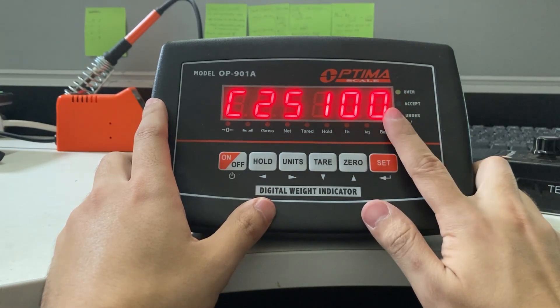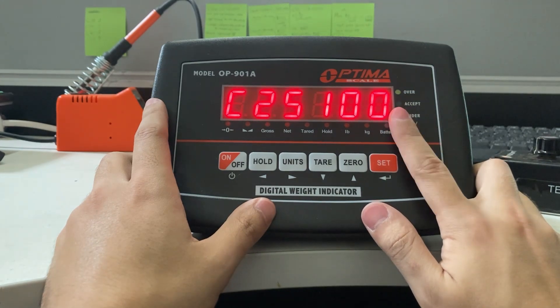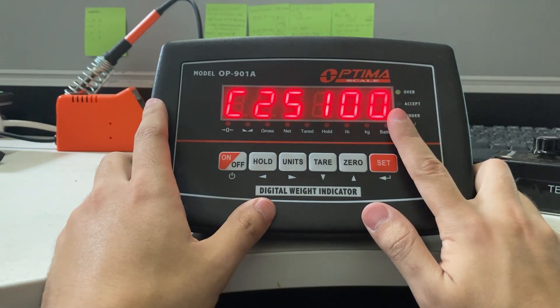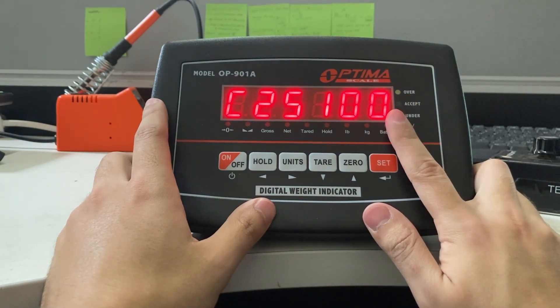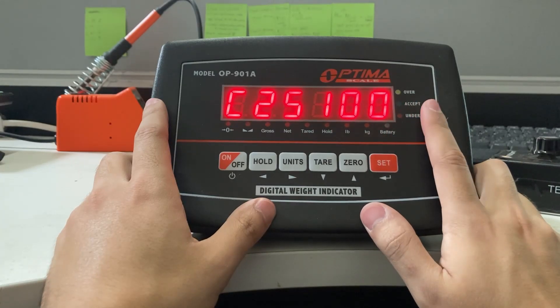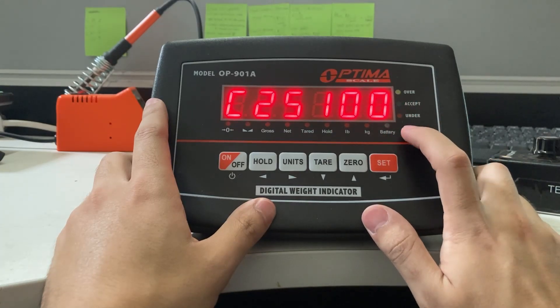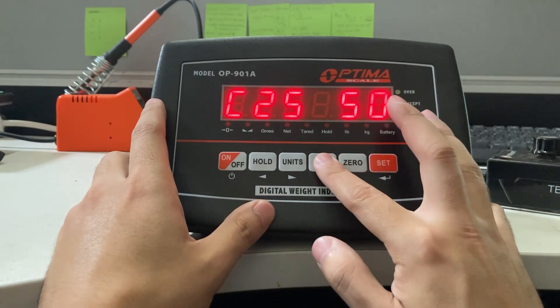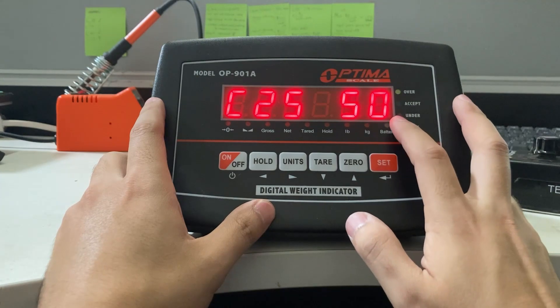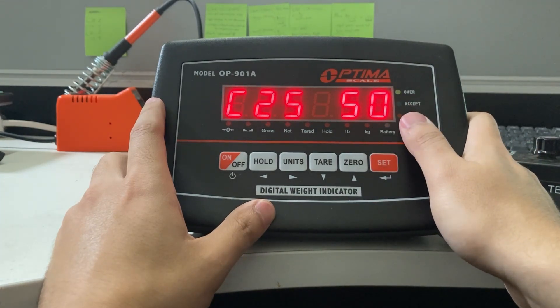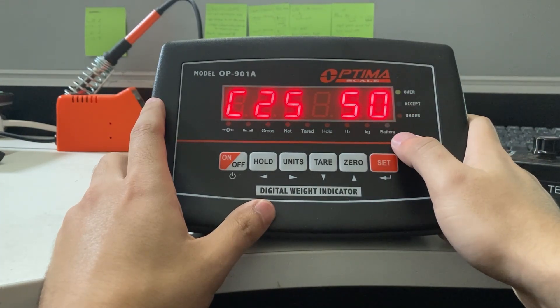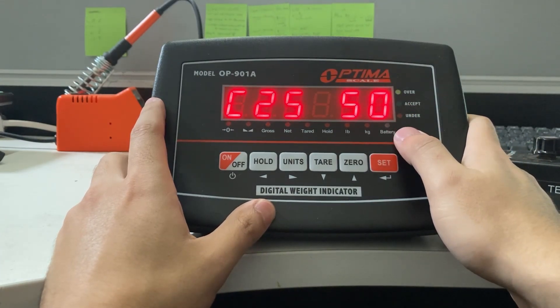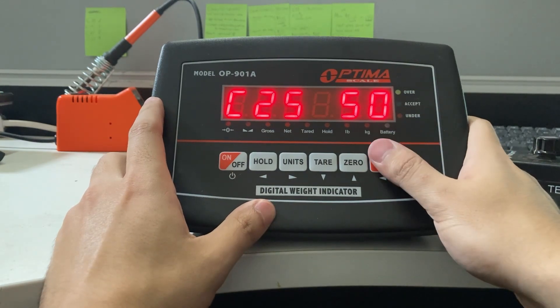What this means is if I have my C04 setting, the max capacity of the indicator, set to 5000, it can go positive 5000 up to negative 5000. If it was set at 50, it could go positive 5000 to negative 2500, which is 50% of the max capacity.